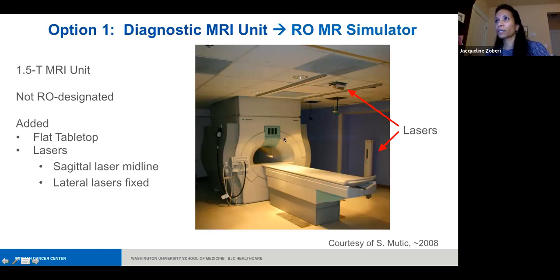For the first one, acquiring your MRI unit, perhaps what you get is a diagnostic scanner, either within your department or outside of it. In our case, we inherited a scanner that was no longer needed by cardiology. It was a 1.5 Tesla unit, not radiation oncology designated, so we had to add a flat tabletop and some lasers to make it radiation oncology friendly.